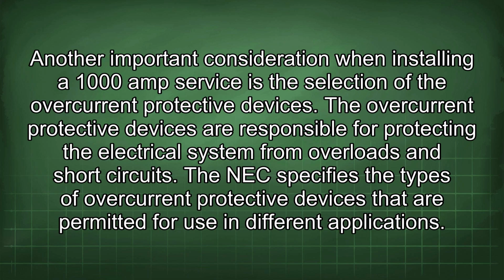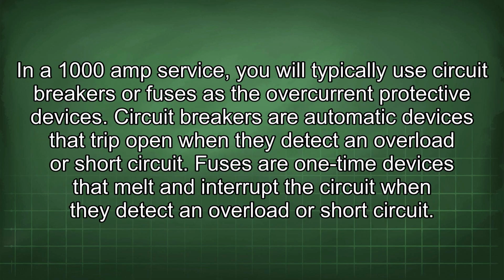Another important consideration when installing a 1000 amp service is the selection of the overcurrent protective devices. The overcurrent protective devices are responsible for protecting the electrical system from overloads and short circuits. The NEC specifies the types of overcurrent protective devices that are permitted for use in different applications. In a 1000 amp service, you will typically use circuit breakers or fuses as the overcurrent protective devices.